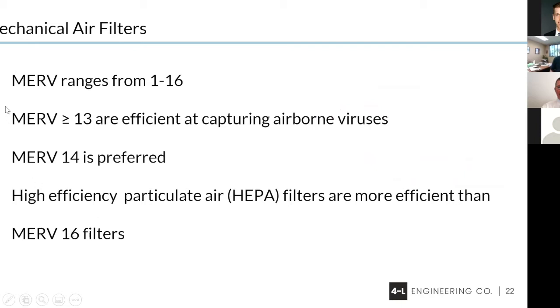When we look at these MERV ratings that run from 1 to 16, we find that the MERV 13 filter can effectively capture the virus and keep it from being distributed in our house. That means every time the air passes across my filter, I'm effectively filtering that air and controlling the virus. If you can get a MERV 14, it does a better job. Some people are going to be talking about HEPA filters, which is a high efficiency particulate air filter. These things are normally in the range of 99.7% efficient, and they take everything out. This would be something we'd use in a hospital.